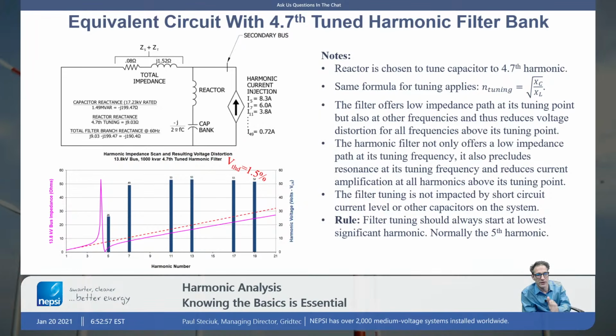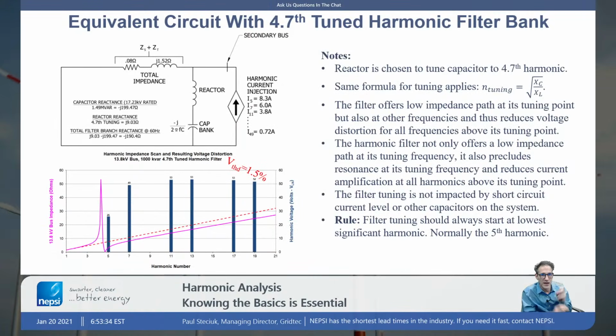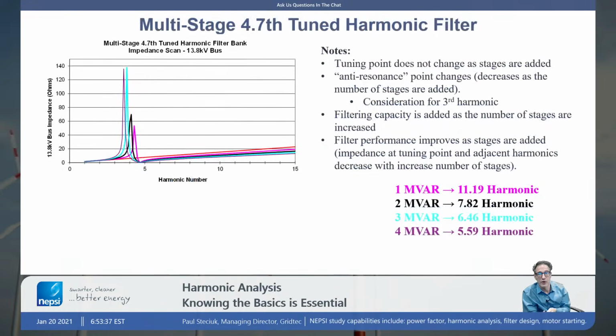If I have a standard network, almost always the first harmonic filter that's put in is a fifth harmonic filter. We might have situations, mine projects that might include cycloconverters, where we might have some harmonics below the fifth harmonic. In that case, you might see a filter put in at the second harmonic or the third harmonic. Another example would be arc furnace applications. The arc furnace has harmonics at the second, third, fourth, and so on. So oftentimes you will see a second harmonic filter. You're doing that because you want your resonant point here to be beneath the first dominant harmonic in the network. So you almost always see a fifth.